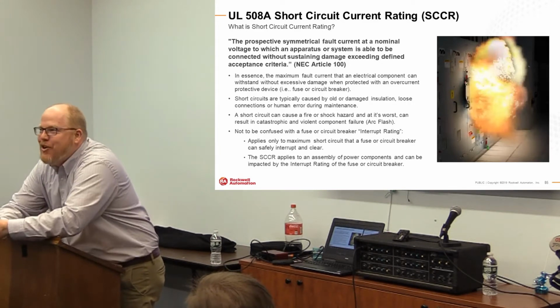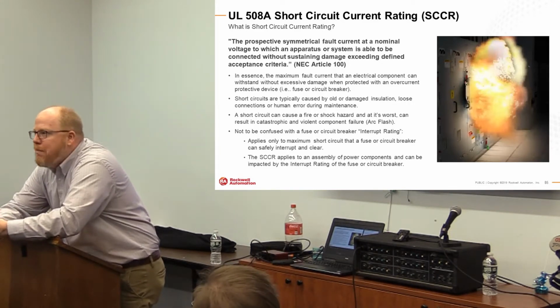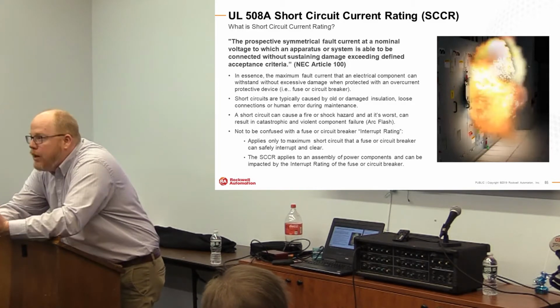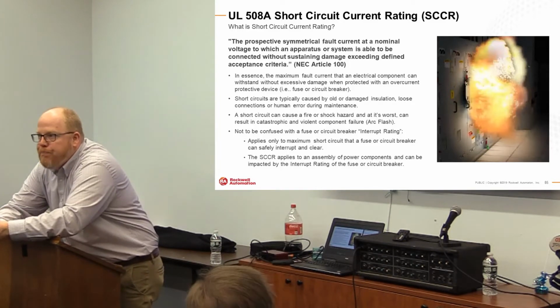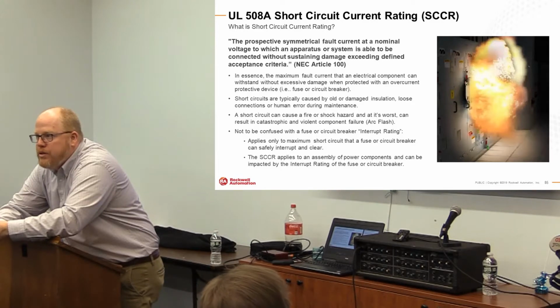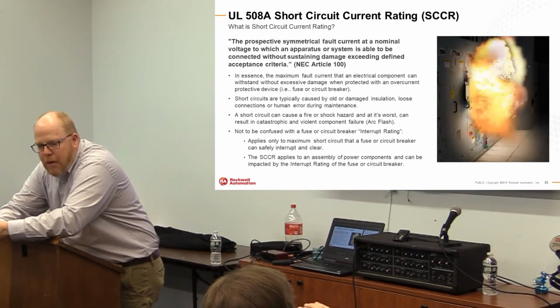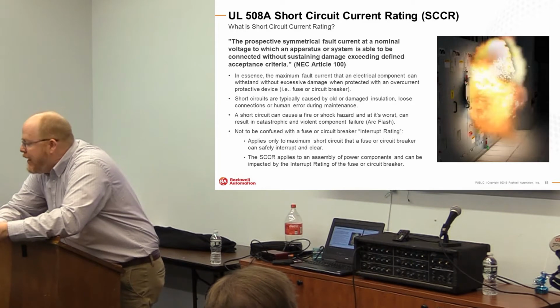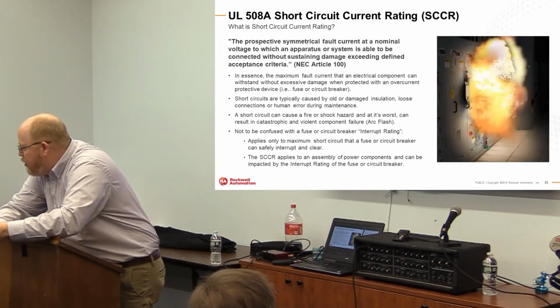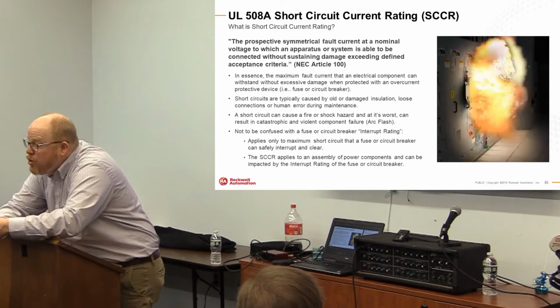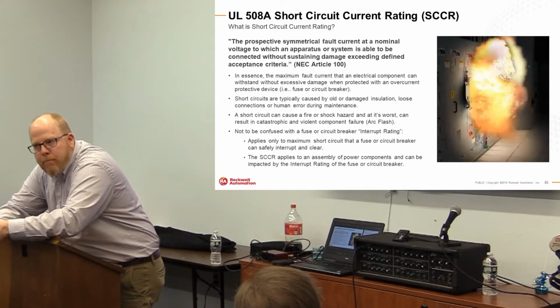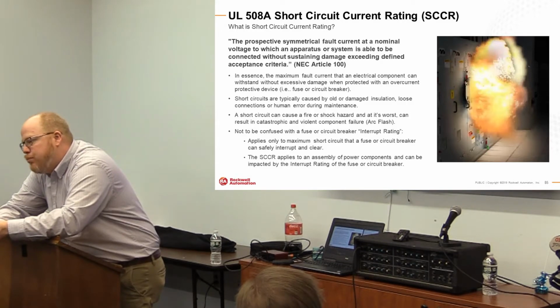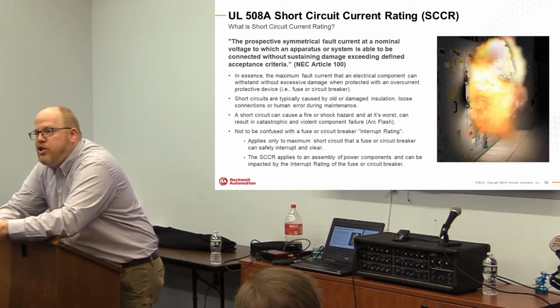All right. So in essence, it's the maximum fault current that a component, like a breaker, can withstand without hurting somebody. And we're really talking here about personnel safety when it comes to maintenance. If you look at the numbers and statistics, what do you think the predominant source or reason for arc flash is? Well, it's up there on the slide. Short circuit. But what's the root cause? People is one. Loose connections and aging infrastructure.